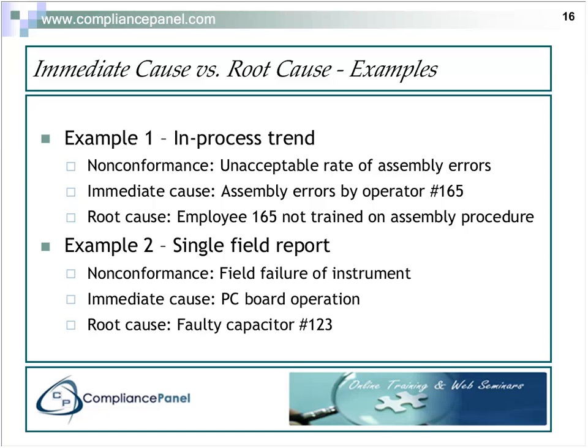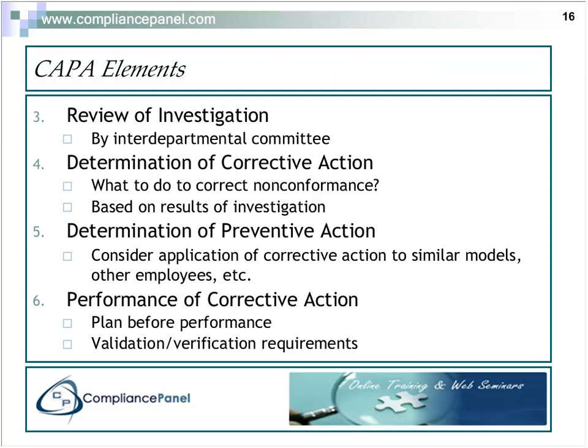Again, just as with the immediate cause previously, that is not a final conclusion. The final conclusion here is that a particular capacitor was faulty, and that the reason the PC board was not working was because of that particular capacitor. That's your root cause. As you can see, root causes versus immediate causes, they are the causes of the immediate cause, and that enables you to implement a much more robust, much more applicable corrective action.